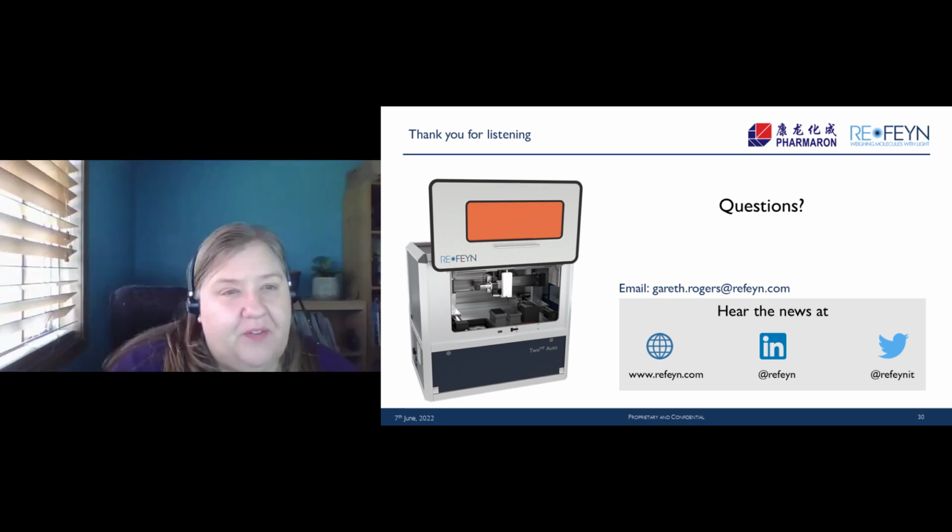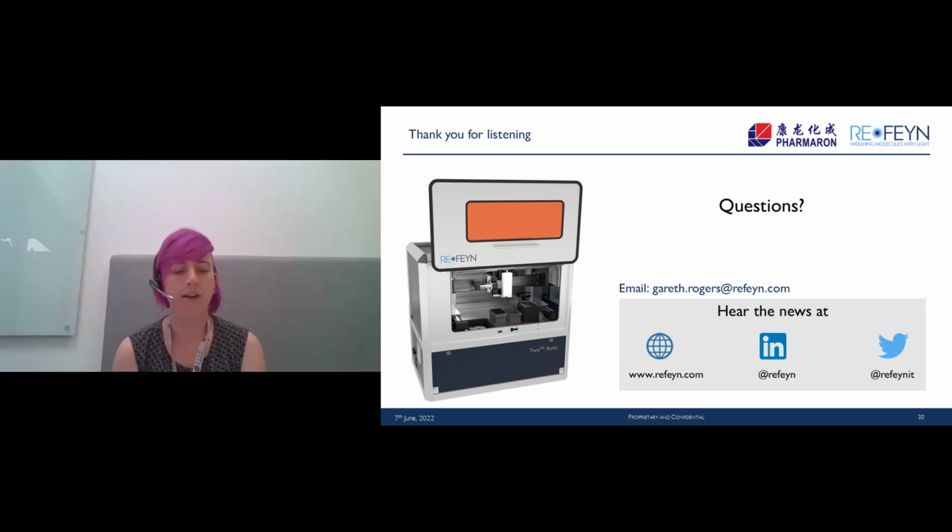Okay. And for Kirsty, what's the biggest benefit of the SamuxMP versus your current technology? In my experience, the biggest challenge in AAV analytics for empty-full analysis is a combination of time and material requirements. And I feel the SamuxMP is able to help with both. For example, as a comparison to the gold standard AUC, we require 400 microliters of material at E to the 12 concentration, and our throughput is only around 7 samples a day with an overnight run. And sample processing can also be time consuming.